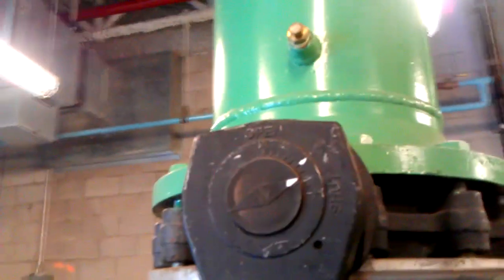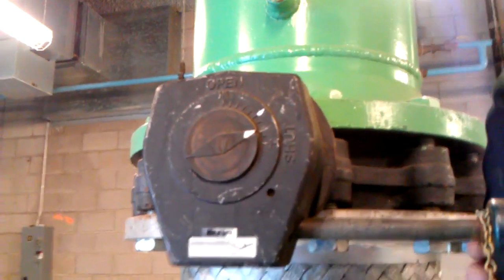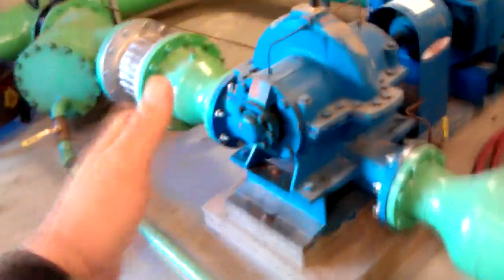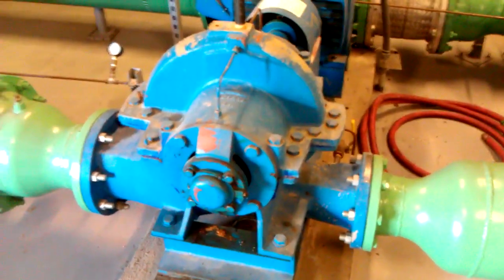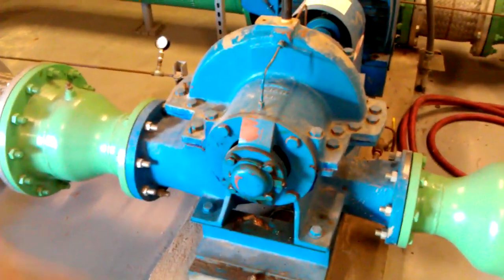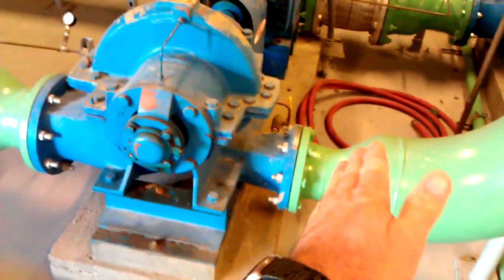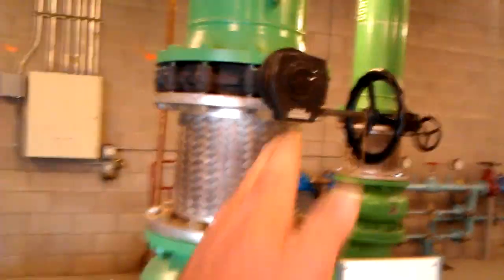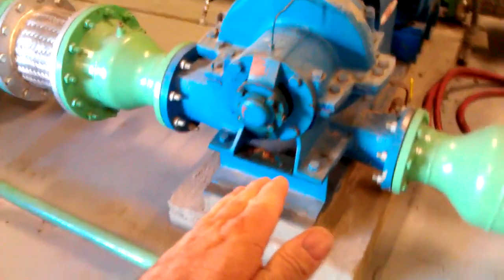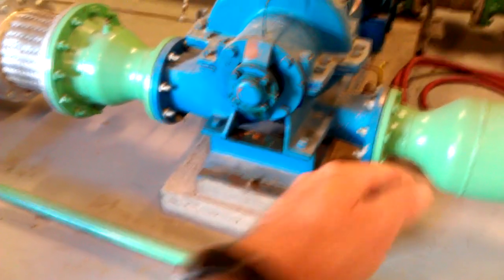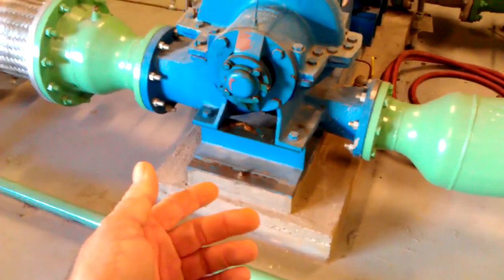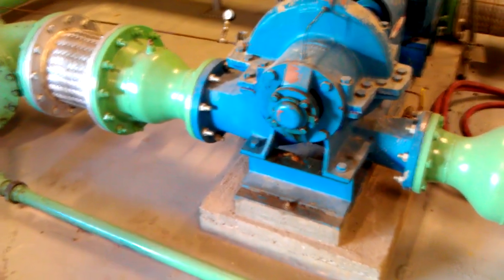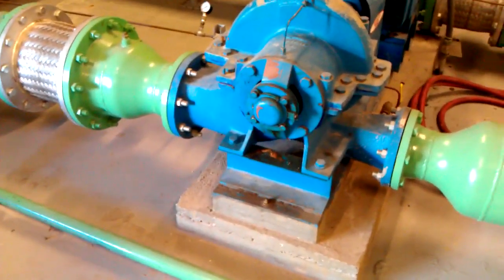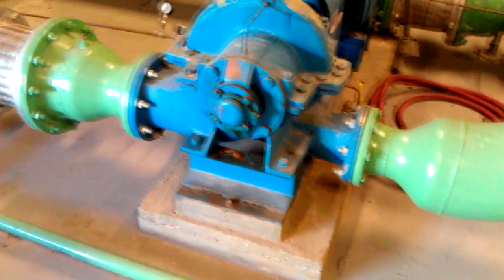One thing I'm going to do is keep these fairly deadheaded a little bit, because see, if you have a restriction on an inlet to a pump and the pump's rated at so much capacity and the inlet is starving, you'll get it to cavitate and it won't want to pump and things like that. So if you butterfly off the discharge a little bit, which is what that is, basically put a lot of back pressure on the outlet. You're limiting how much water can go through that pump, even though it's running at the same speed. And that way, if you have a restricted inlet, it won't act up, cavitate or do all that weird stuff.